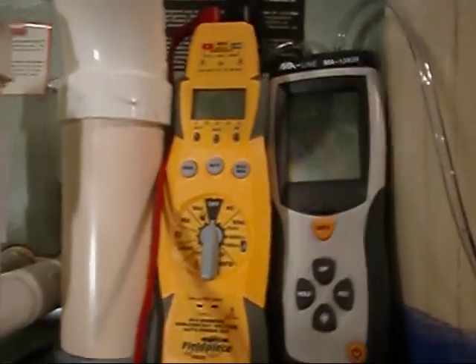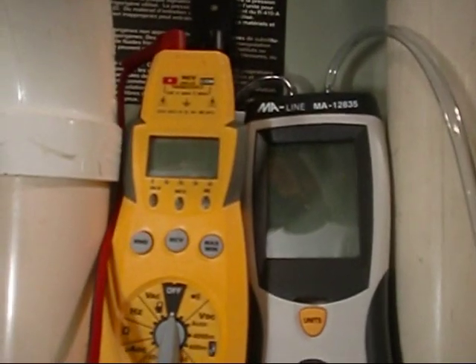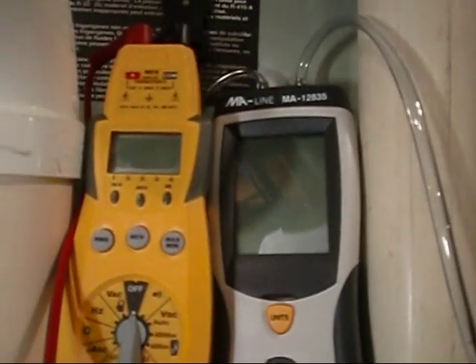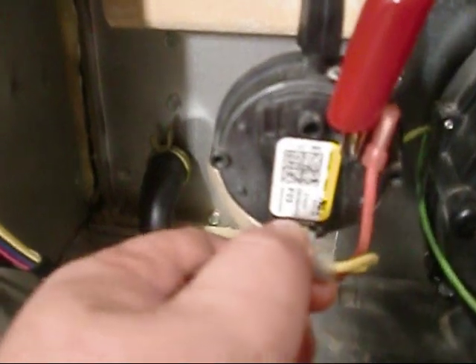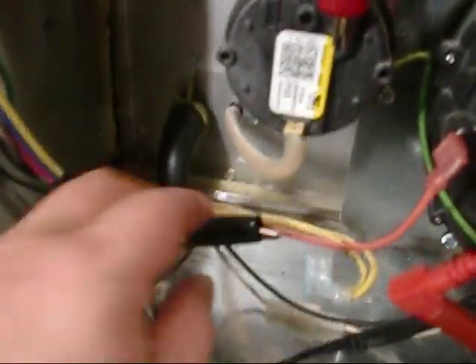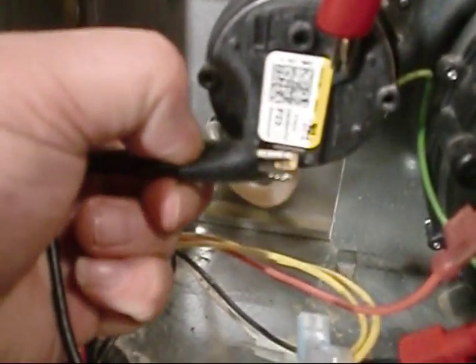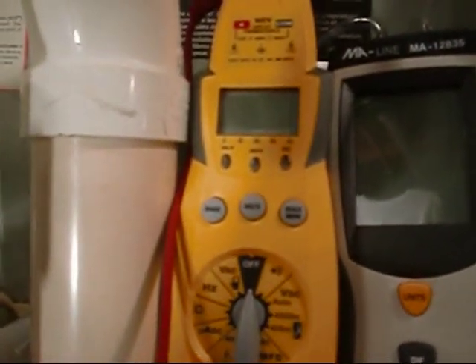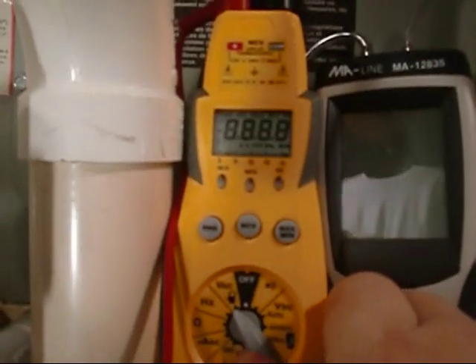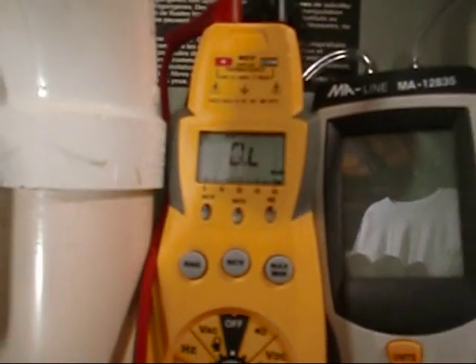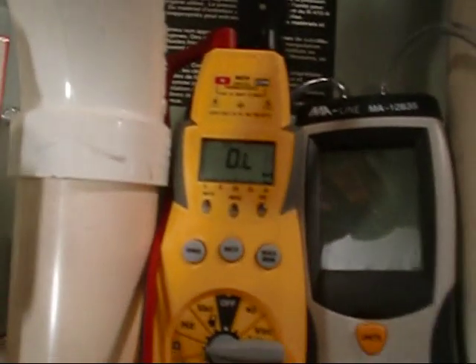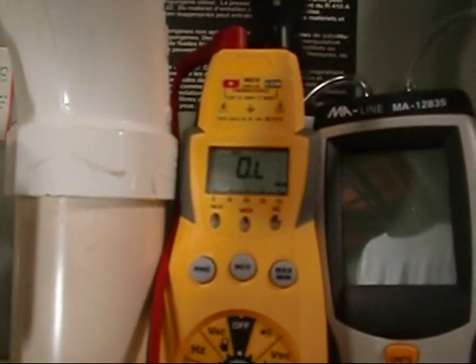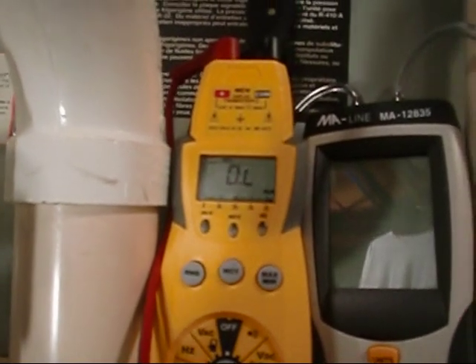Before we hook the manometer up and do our little electrical test, our voltage test with our field piece and get all these tubes and T's hooked up here to this pressure switch, there's another quick test we can do real quick. We'll just take off these spade terminals off our pressure switch there, and got the alligator clip hooked to that terminal, and I'm going to hook this one to this terminal.